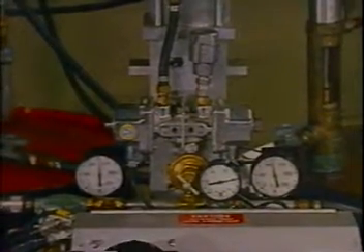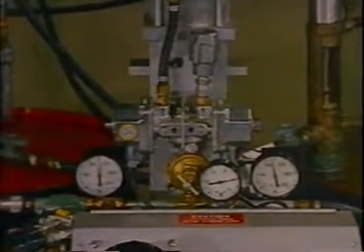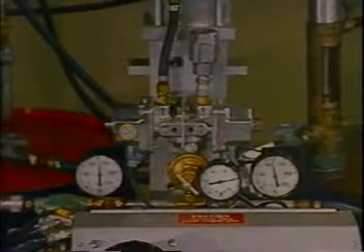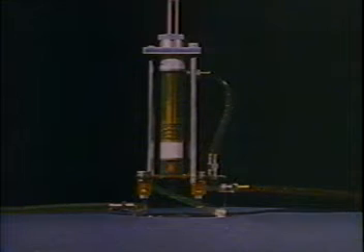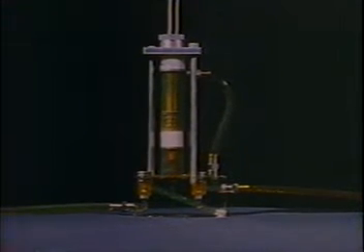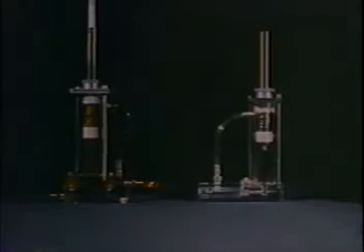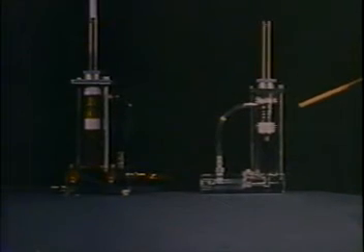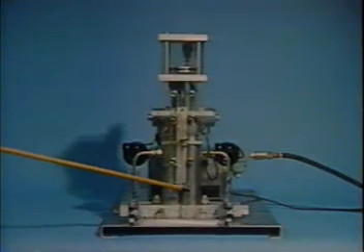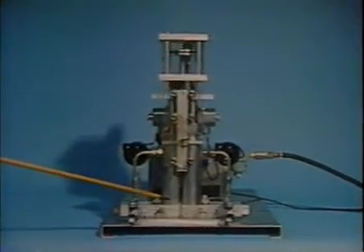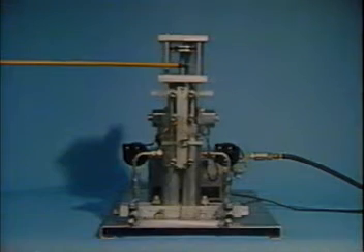To fulfill the requirements of mechanical thrust and efficient liquid seals necessary to develop working pressures of up to 1,000 pounds per square inch, the design of actual production proportioning pumps is somewhat different than the visible model demonstration pump used thus far, and is more accurately represented by this visible model where piston shaft and pump cylinder are located at the end of the pump base, allowing two piston shafts to be brought into close alignment with the thrust of the common drive system.